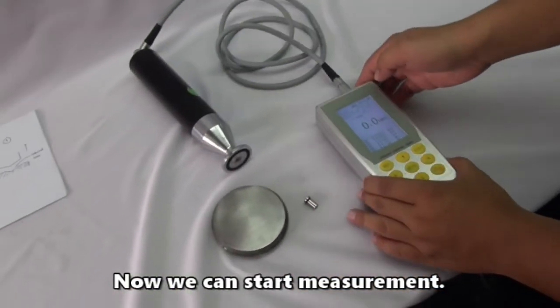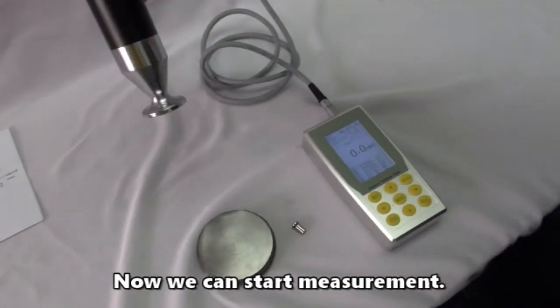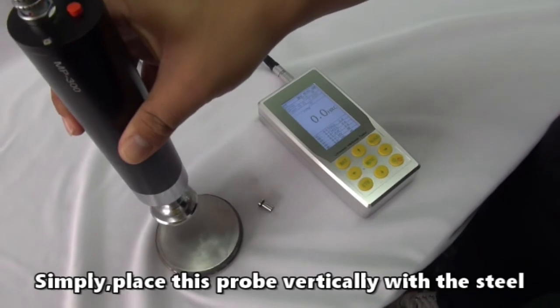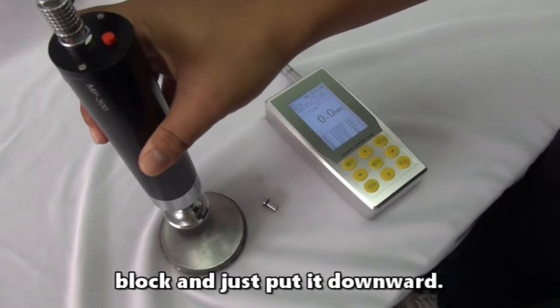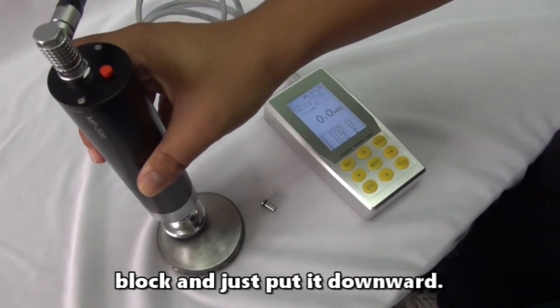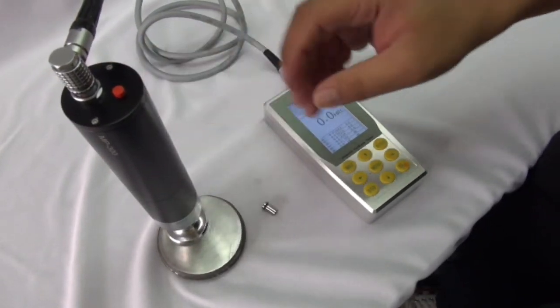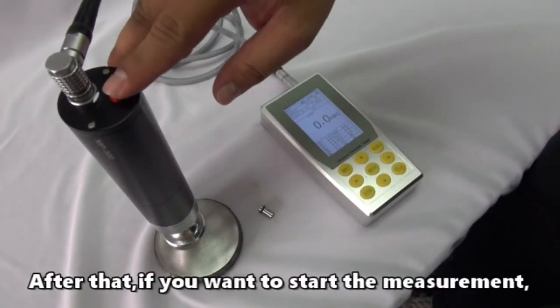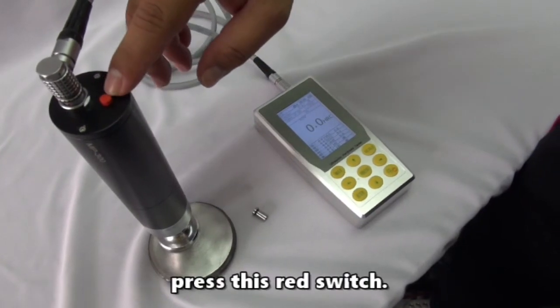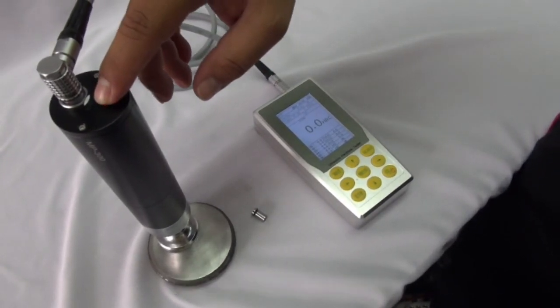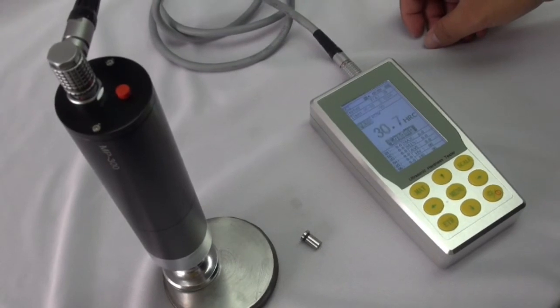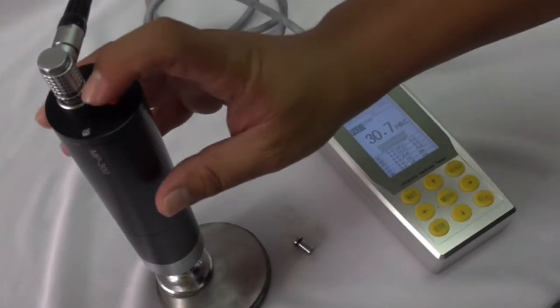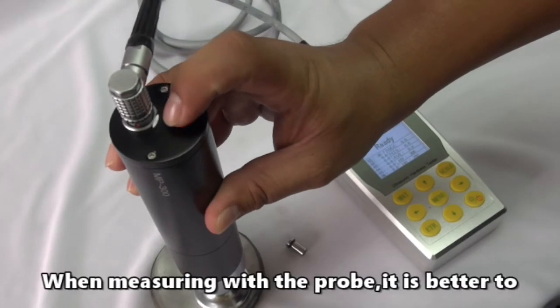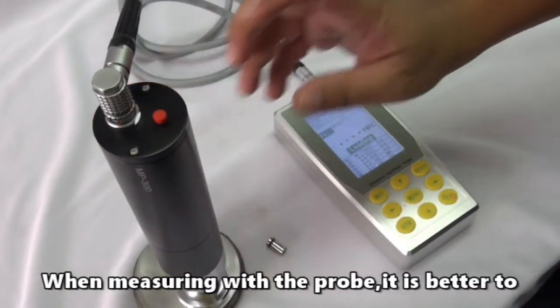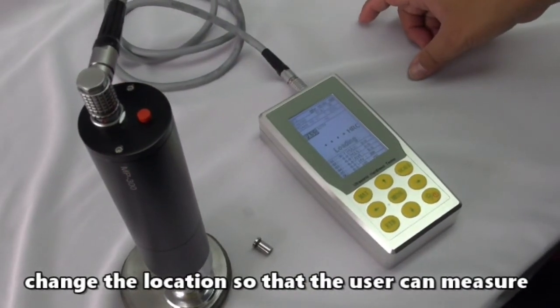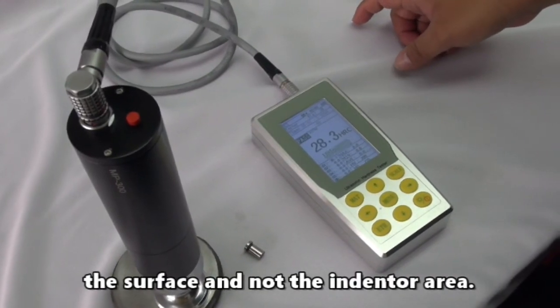Now we can start the measurement. Simply place this probe vertically on the steel block and push it downward. After that, if you want to start a measurement, press this red switch. When measuring with the probe, it is better to change the location so the user can measure a fresh surface and not the indented area.